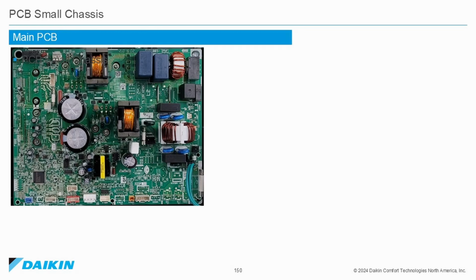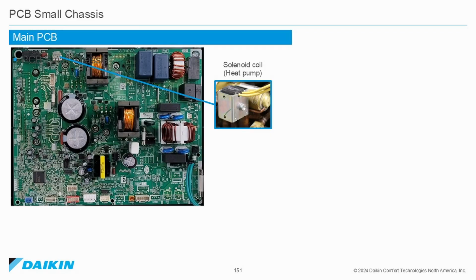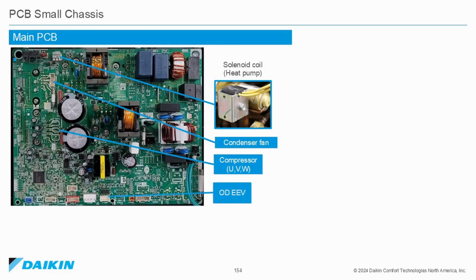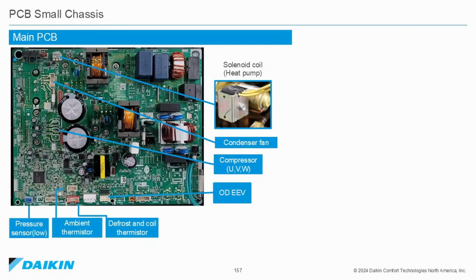Printed circuit boards on small chassis units. The main printed circuit board. Here are the connection locations for the solenoid coil for the heat pump, condenser fan, compressor, terminals U, V, and W, outdoor electronic expansion valve, low pressure sensor, ambient thermistor, defrost and coil temperature thermistor, high pressure switch.